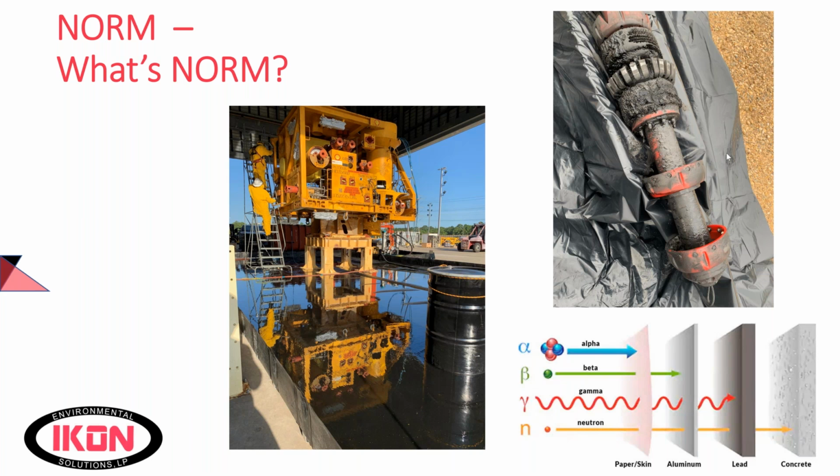So I was going to address this later, but I think we should probably hit it now. When we're talking about counts, what are we talking about? When you hold a detector up, depending on what detector you have will depend on how it reads out. When you're measuring gamma radiation and X radiation, you're typically going to be measuring exposure rate in microroentgen per hour. Everybody calls it dose rate. It's actually exposure rate, but it pretty much correlates 1-to-1 to true dose also.